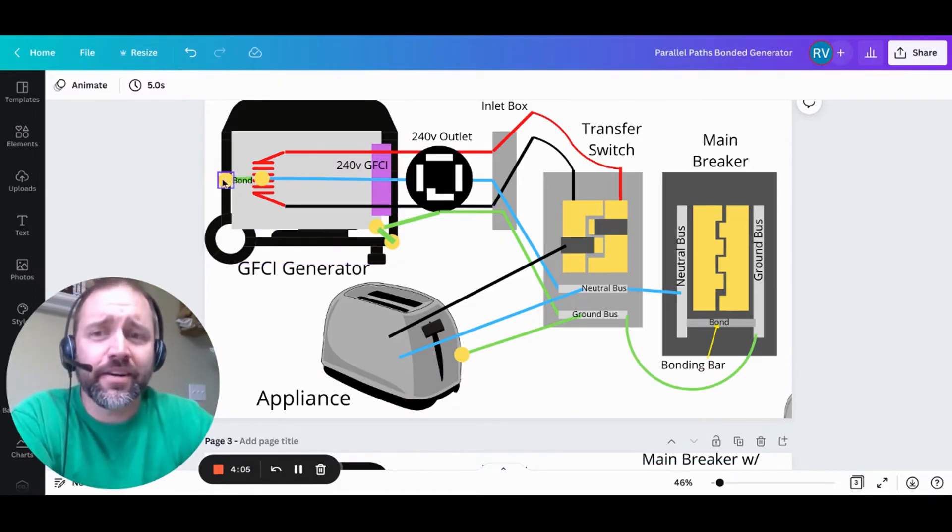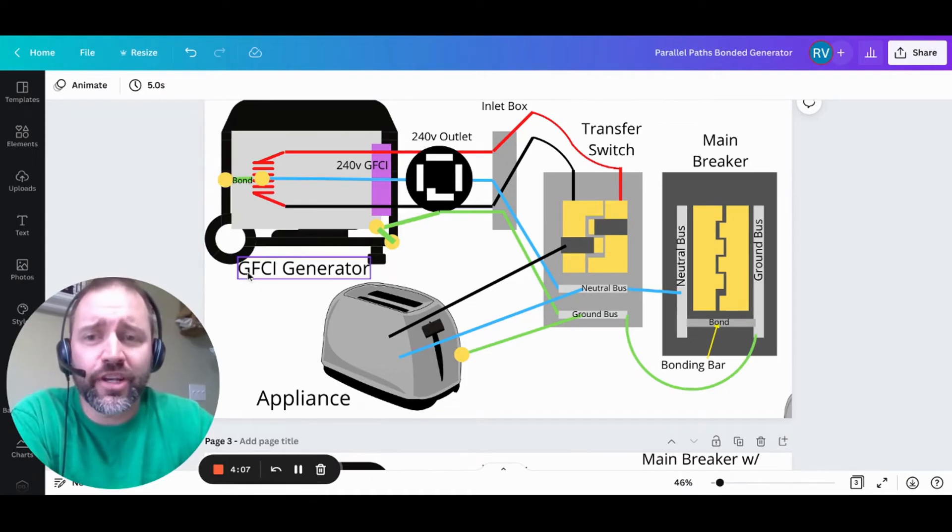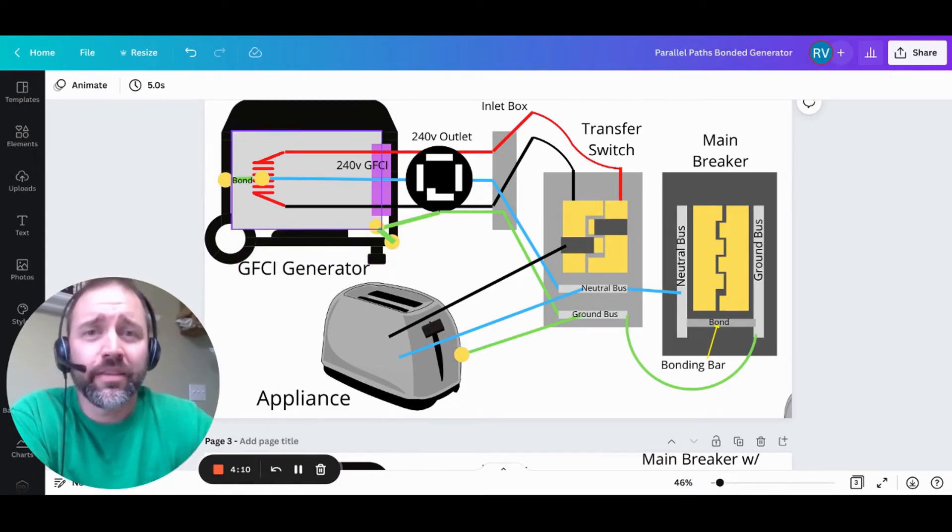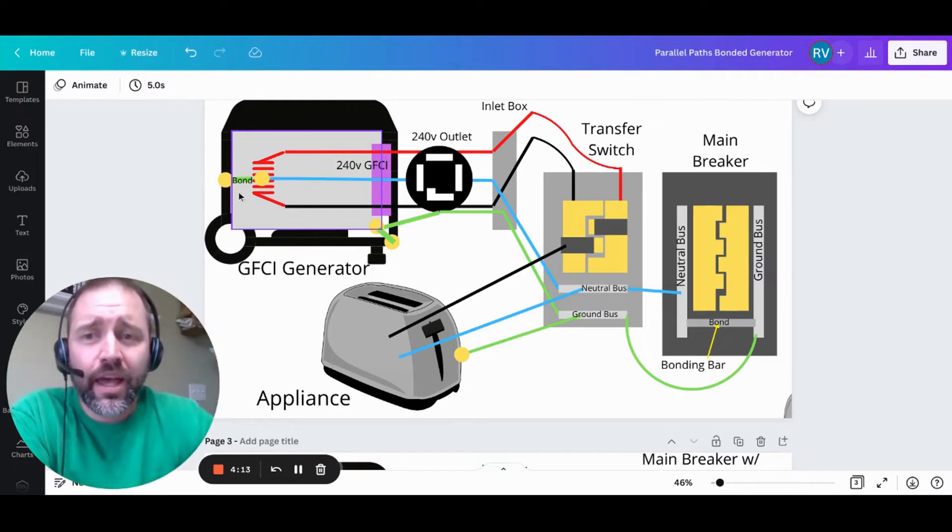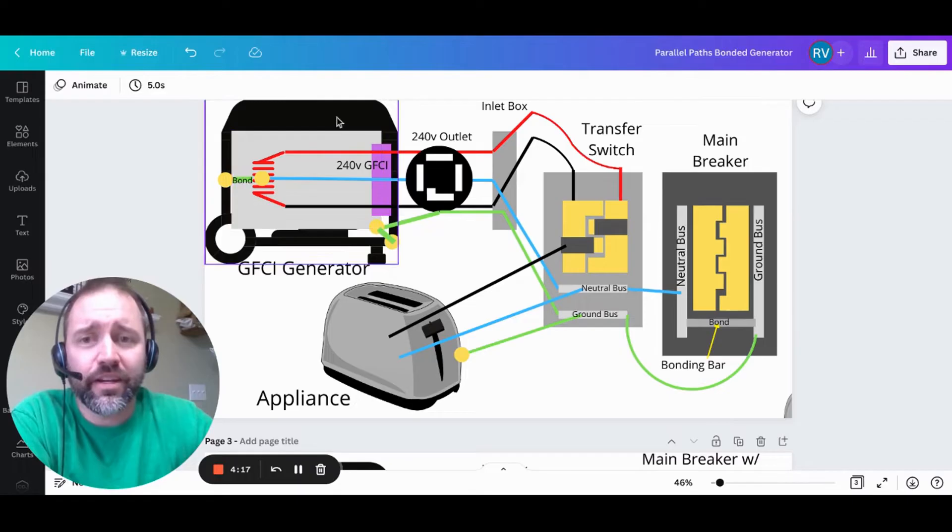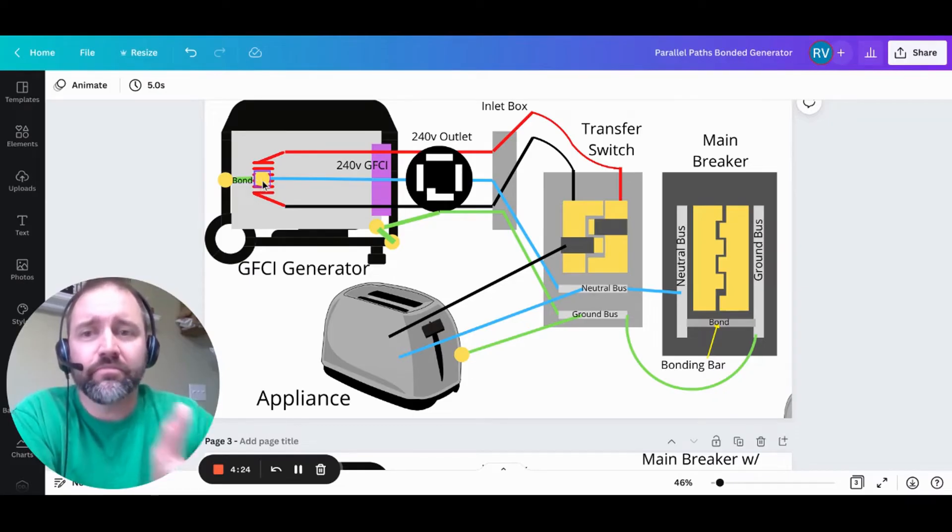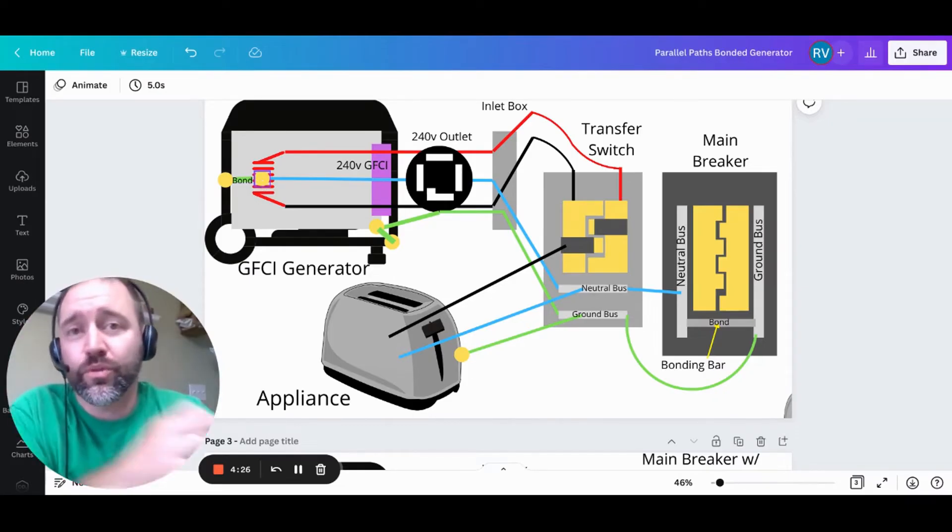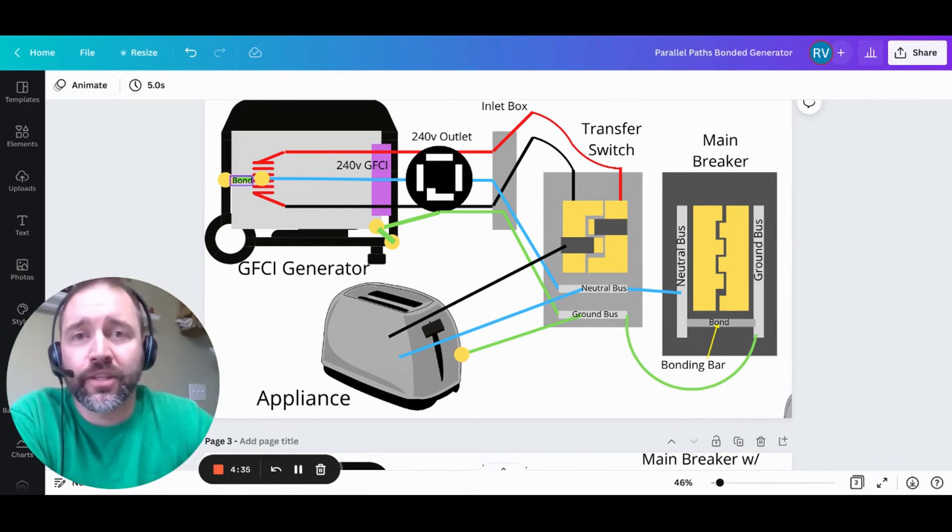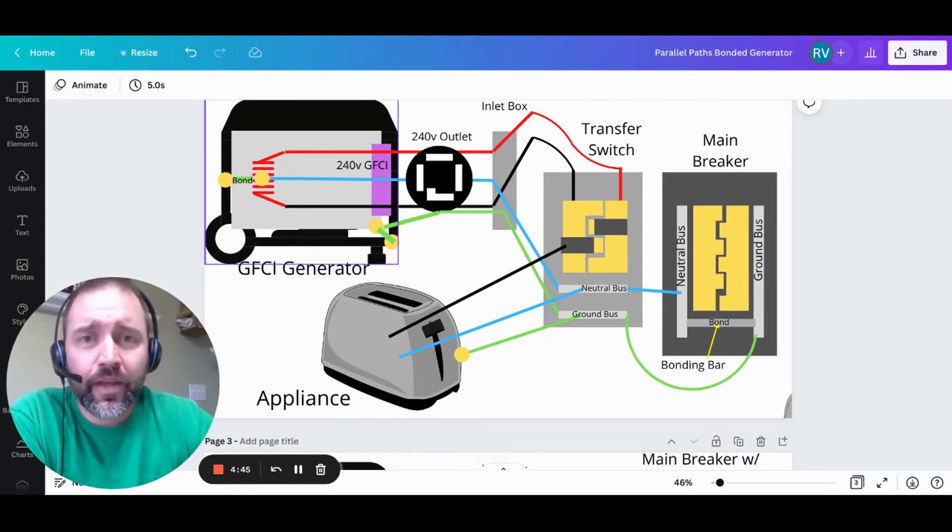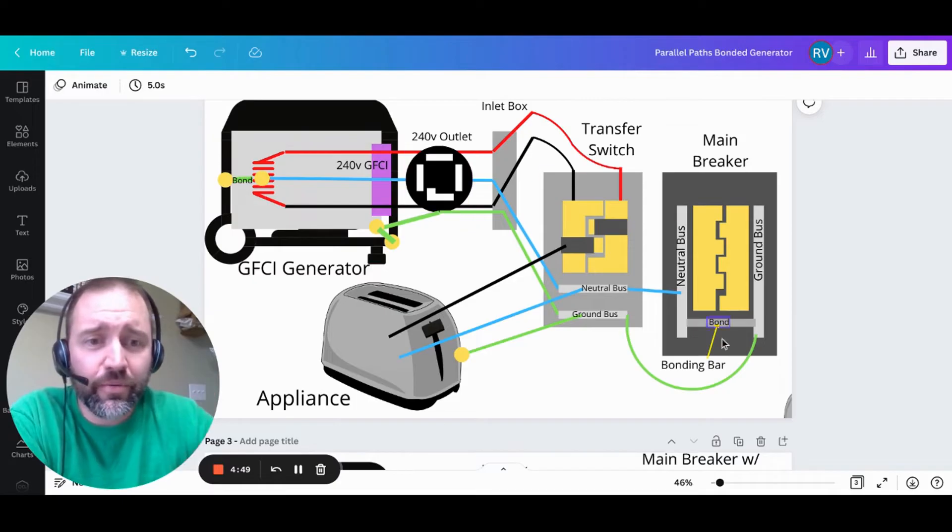You have a bond here on the back of your GFCI protected generator. It's usually under the alternator cap. There's a jumper that goes from the ground to the neutral, and what this basically is, it's a point at which the ground, everything here on the generator, and the ground wire, and the frame, and everything, it makes contact with the neutral as an alternate source back to complete the circuit. Usually, this is used when there is a fault in the system, but in this case, it's going to come back to bite us, and the reason for that is that we have a bond here, but if you look all the way on the right side, we have another bond here.